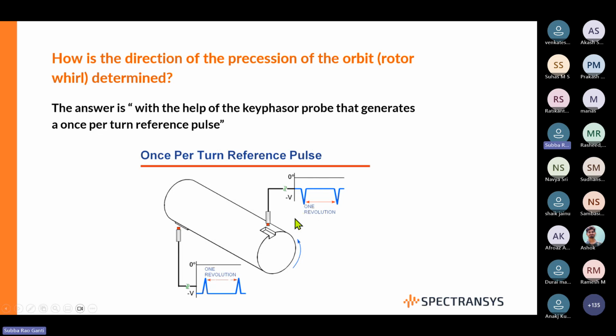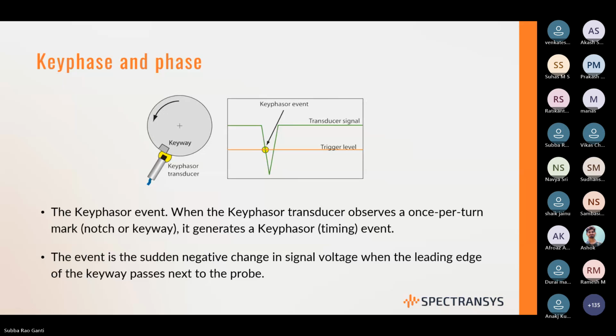When the projection is there, it's a negative going pulse. When the keyway is there, it's a negative going pulse, and when the projection is there, it's a positive going pulse. The distance between two consecutive pulses equals the time taken for one rotation. This is how the key phasor generates reference pulses for rotation, for phase measurement. This is an extended understanding of it.